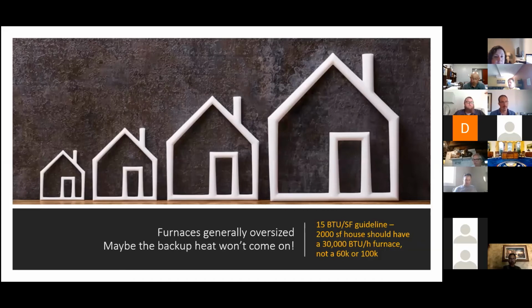I know for my house, I don't need a 100,000 BTU furnace because we really should be at about, according to Dave, our resident energy engineer, about 15 BTUs per square foot. Why do I have such a huge furnace? I don't know. Maybe that's the contractor's rule of thumb, but I should be able to get away with 30,000 BTUs for a 2,000 square foot home. But generally you see 40, 60, or 100, they're generally oversized. Now this 15 BTUs per square foot makes a big difference because we're tighter on the heating side than we are when we have a giant gas furnace. So something to think about.